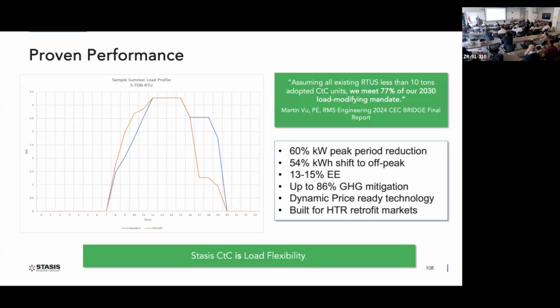In a 15-minute period where you create demand, we can limit our compressor run times to no more than 6 minutes. That's on the worst day, giving you 60%. We are shifting between 50 and 55% of kWh from peak to off-peak. Because we're now cooling and charging the media at a lower temperature, we're able to bring up energy efficiency by 10 to 15%.